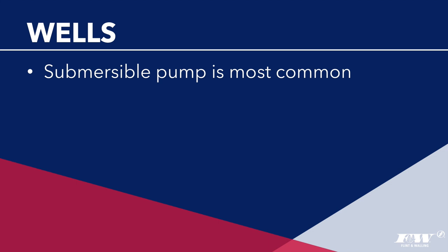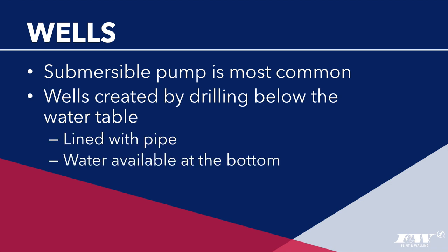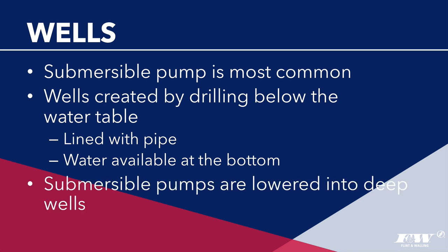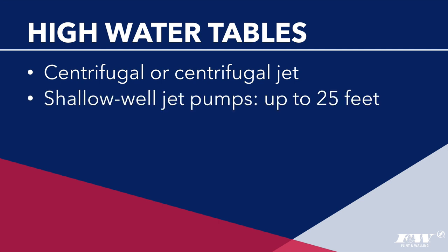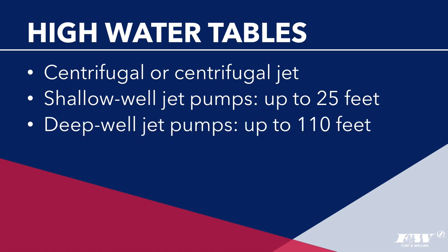If your water source is a well, the most common pump used is a submersible. A well is drilled into the ground to reach below the water table. For deep wells, a submersible pump is lowered down and submerged in the water, pushing it to the surface. For areas with high water tables, you can use a centrifugal or centrifugal jet pump instead. Shallow well jet pumps work for sources up to 25 feet deep; deep well jet pumps can be used for sources up to 110 feet deep.